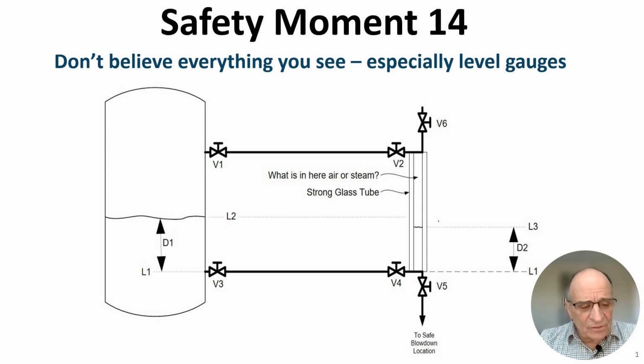Now, here's a picture of a vessel, and it's connected to a gauge glass where you could see a liquid level and the vapor side connected to the top. Typically we would expect this level to be the same as that level, but I'm showing it's not. Why is it not the same level? Well, is the density of this fluid the same as the density of this fluid? It may not be. And here's one of the reasons.